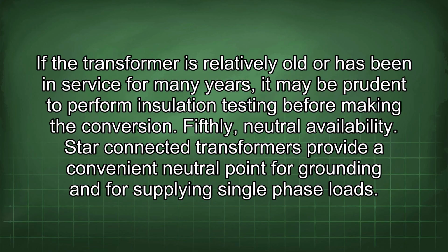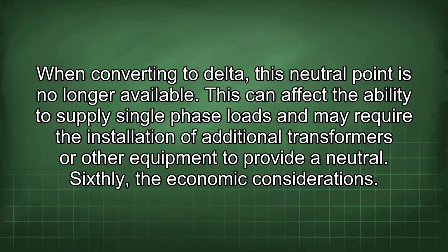Fifthly, neutral availability. Star-connected transformers provide a convenient neutral point for grounding and for supplying single-phase loads. When converting to delta, this neutral point is no longer available. This can affect the ability to supply single-phase loads and may require the installation of additional transformers or other equipment to provide a neutral.